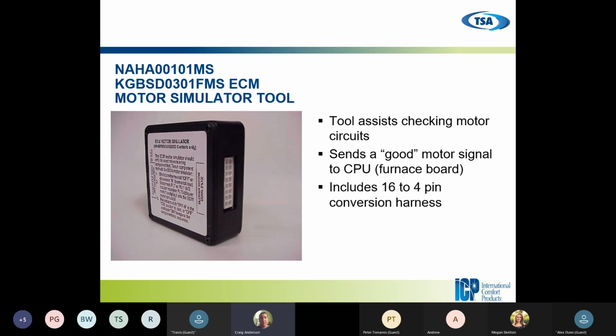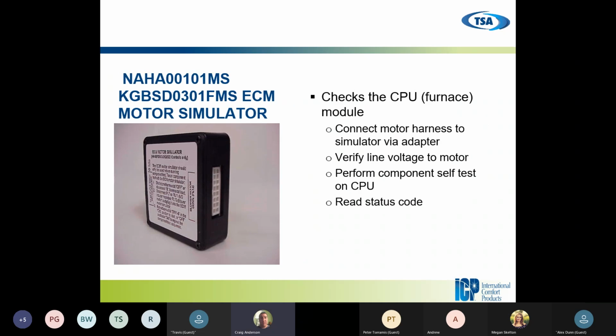We've eliminated the fan motor because we're telling the board we have a good motor. Something else is still going on. So it's taking that guesswork and that testing out of the equation for you just by plugging it in. So connect the motor harness to the simulator, verify that we have the line voltage, 115 volts at all times. Perform your self-component test, SW1-6. And then let's see what the status code says on our board. This little device is telling us we have a good motor, so what else is happening?